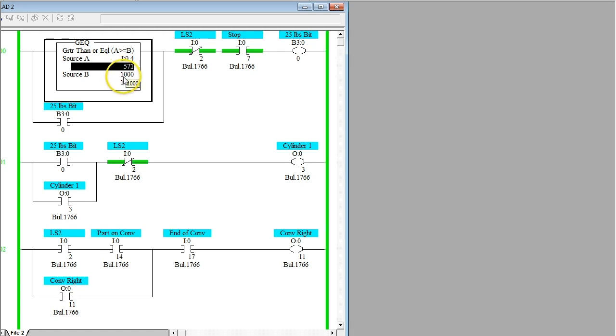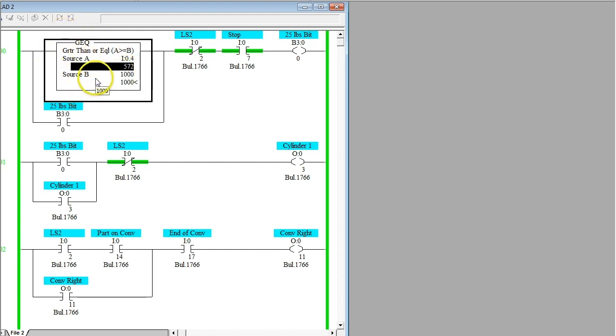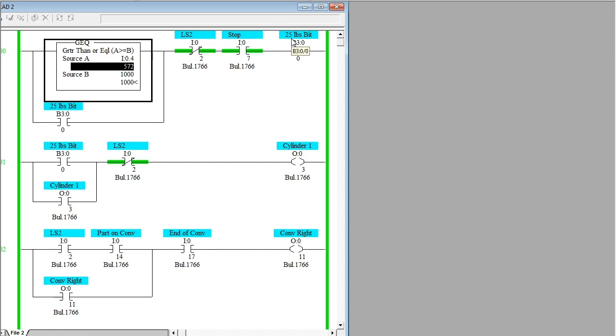What I have is the setup where when that analog signal sends over a voltage that will be interpreted as a thousand, this greater than will become true. When that goes true, it's going to activate this B3 which represents the 25 pound bit, representing that this analog signal is a strain gauge and it has had 25 pounds put onto it.